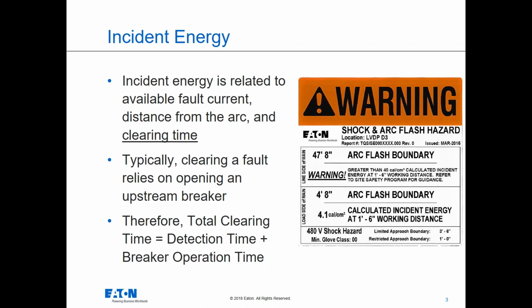The current rules with NFPA 70E dictate that incident energy shows up on an arc flash hazard and safety label, and that's what we're showing on this slide. So in the example that's here, there's a 4.1 calorie incident energy at a 1 foot 6 inch, or 18-inch, working distance. That working distance is very common because that's basically your arm's length from the front of a human torso to a hand where you're operating a breaker toggle or a push button on a circuit breaker.